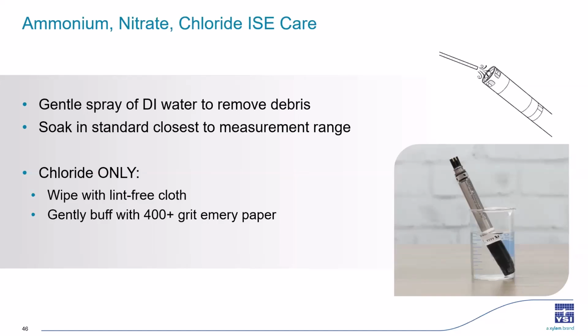After the soak, go ahead and let it air dry because you don't want to wipe the tip. Those membranes are fragile and you don't want to scratch it or damage it. And only the chloride ISE can be gently wiped with a lint-free cloth. If you do see deposits, you can use a fine emery paper to gently buff off the surface, but that will only be for the chloride ISE.